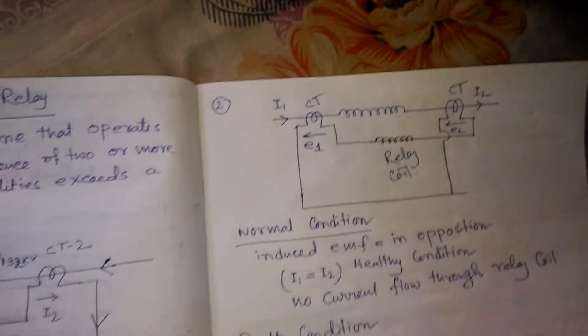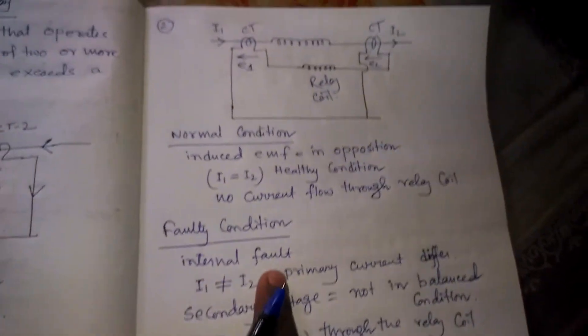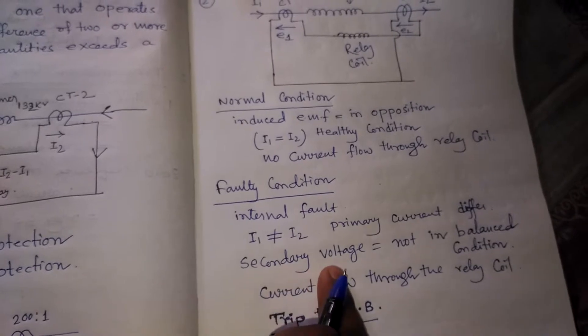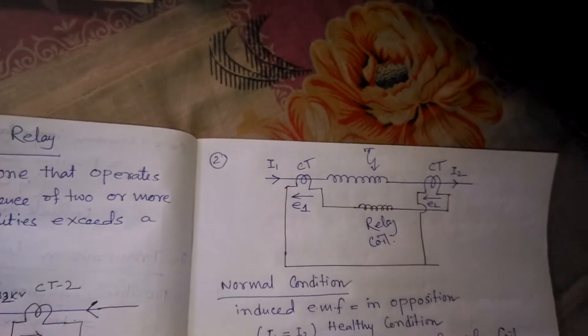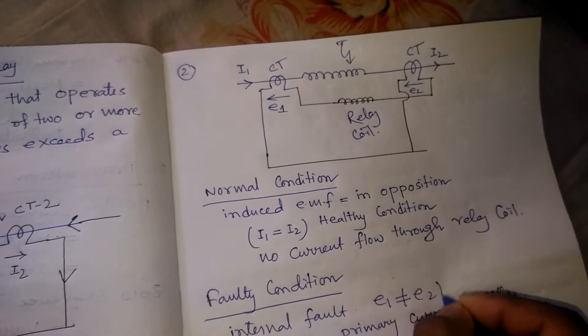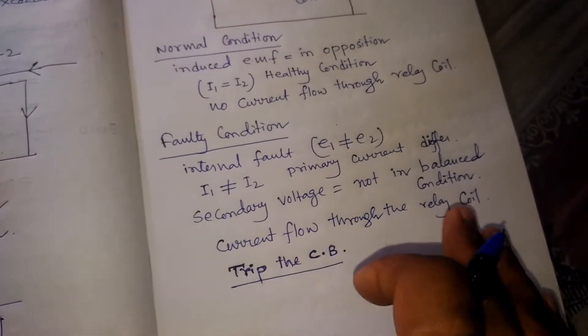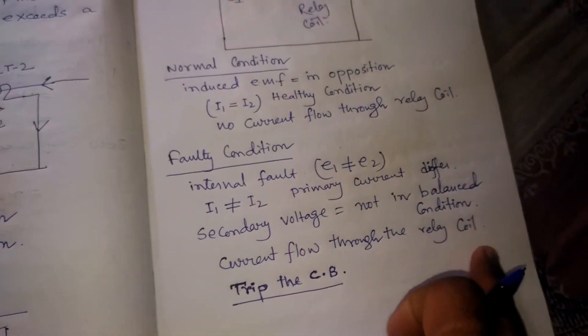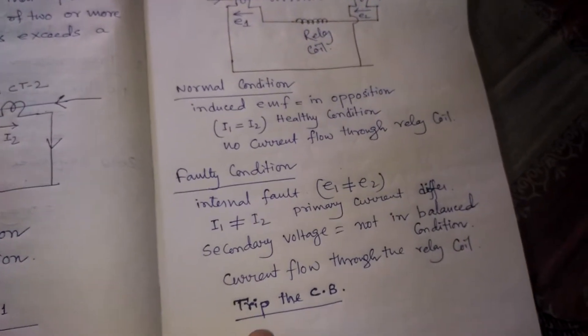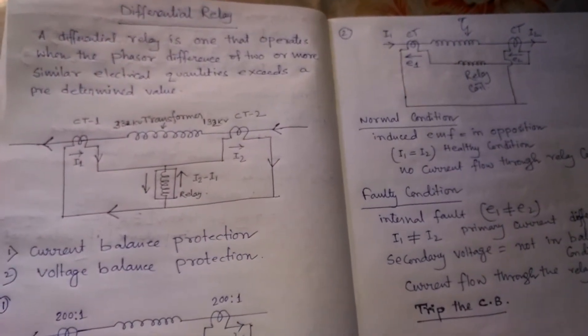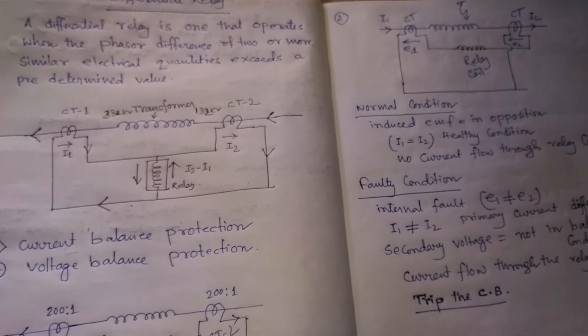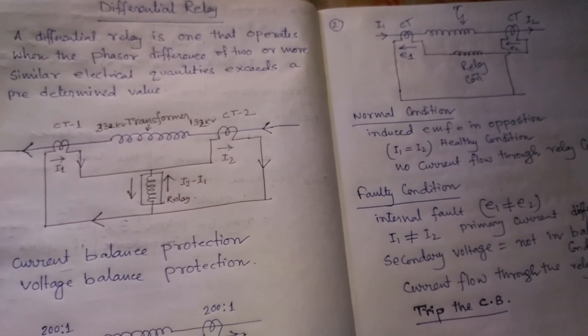In the faulty condition, if any internal fault occurs, I1 is not equal to I2 — the primary current differs from the secondary current. So the secondary voltage is not in balanced condition: E1 is not equal to E2. Current will flow to the relay coil and trip the circuit breaker. Today we discussed the differential relay, which has very important applications in transformers, alternators, etc. Thank you very much.